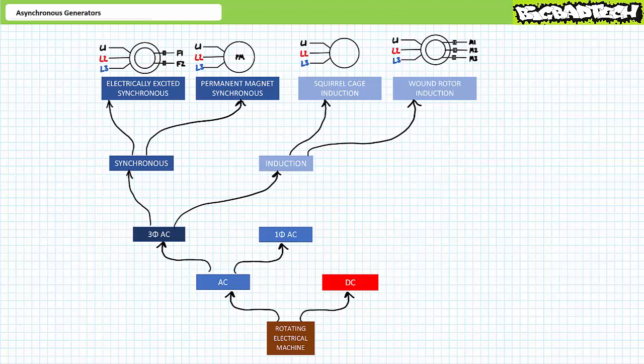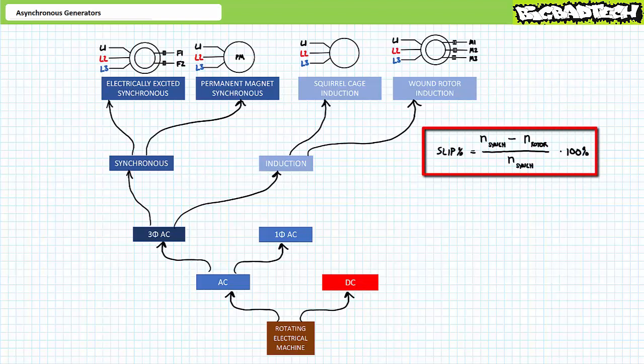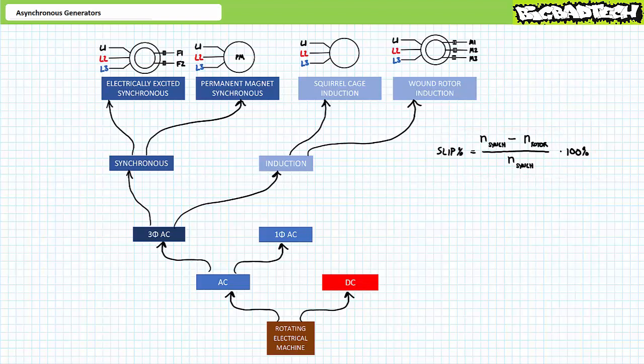This is essentially opposite of what we learned about squirrel cage induction motors. The rotors of squirrel cage induction motors must necessarily lag the synchronous speed produced by the stator, even in the unloaded state. This degree of lag is sometimes expressed as slip, being a percentage of synchronous speed. Asynchronous generators must also exhibit slip to export electrical power, only they must do so in a leading fashion. Only when some outside prime mover with sufficient mechanical power grabs the shaft and accelerates it faster than the stator's synchronous speed does it become a generator.